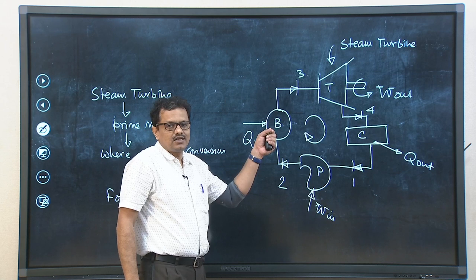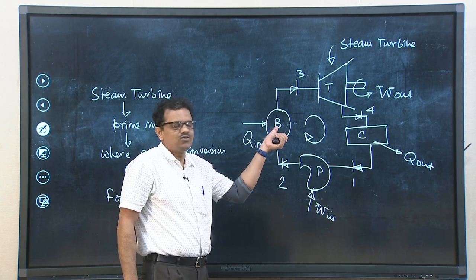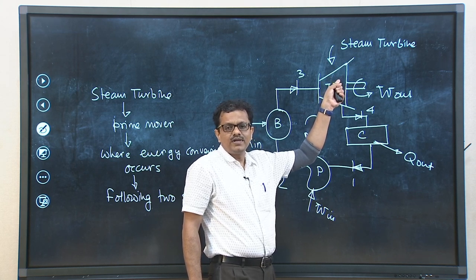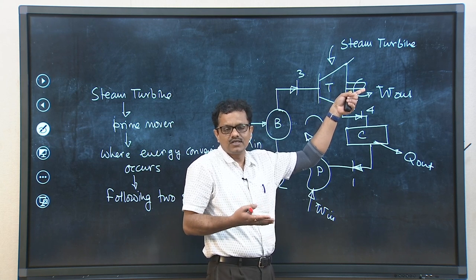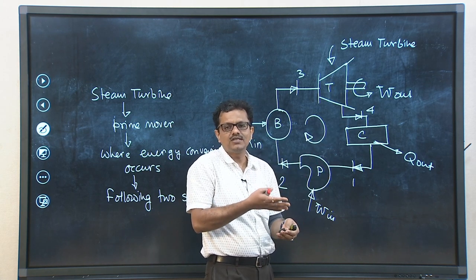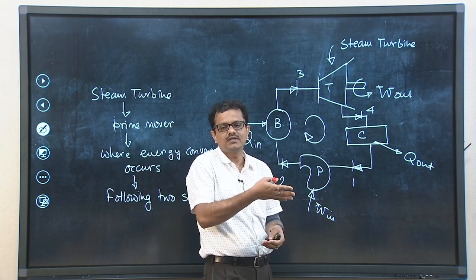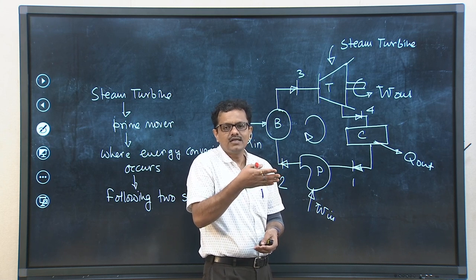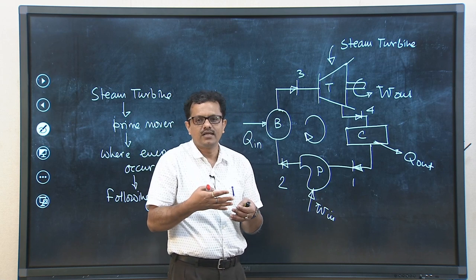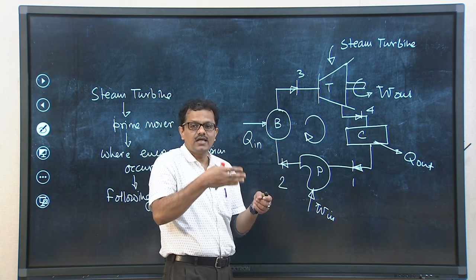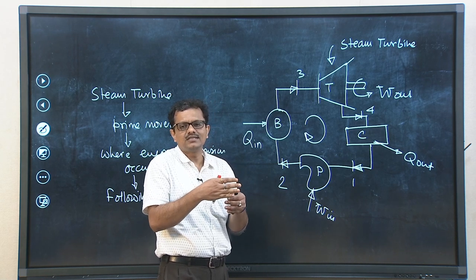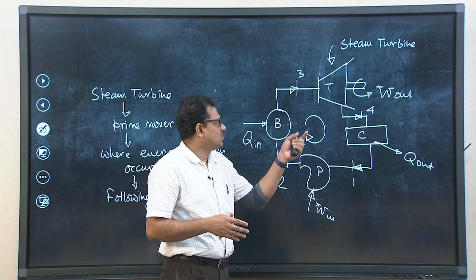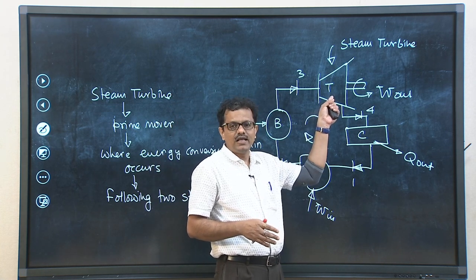Steam produced inside the boiler is not taken directly into the turbine. Instead, there are flow nozzles and steam is taken first into the flow nozzle. While passing through the flow nozzle it expands, and the sole purpose of the flow nozzle is to increase the kinetic energy of steam before it strikes the turbine blade. The kinetic energy of the steam jet must be very high before it leaves the nozzle and strikes the turbine blades.